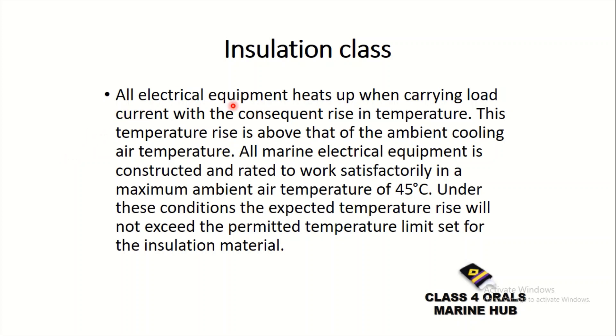All electrical equipment heats up when carrying load current, with a consequent rise in temperature. This temperature rises above that of the ambient cooling air temperature. All marine electrical equipment is constructed and rated to work satisfactorily in a maximum ambient temperature of 45 degrees centigrade.